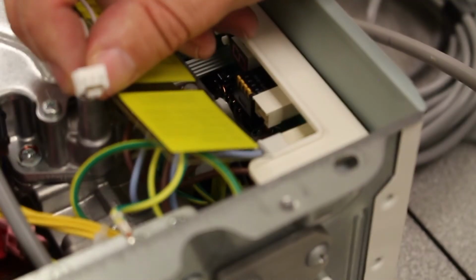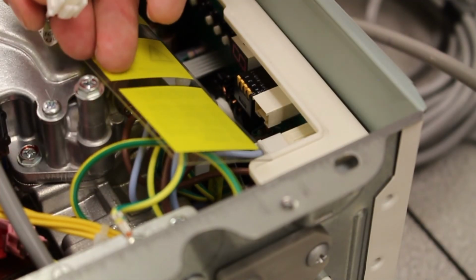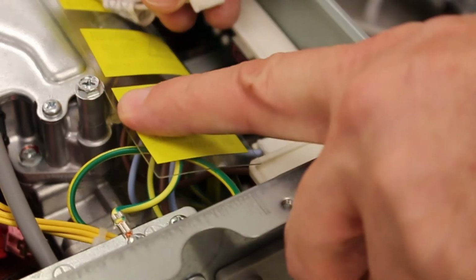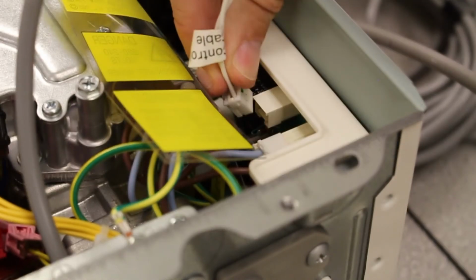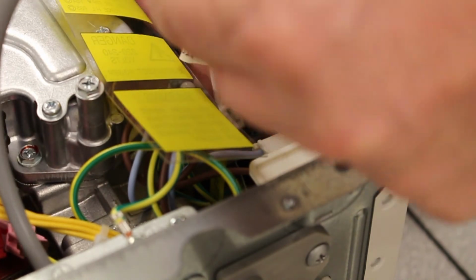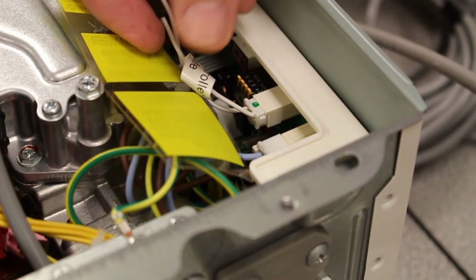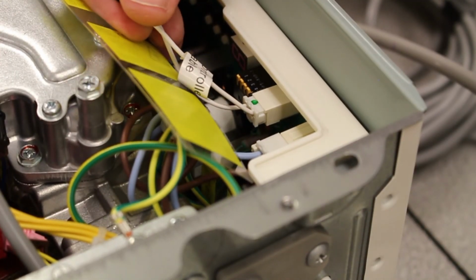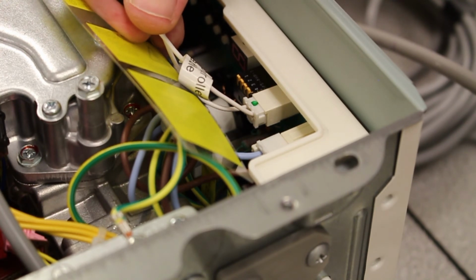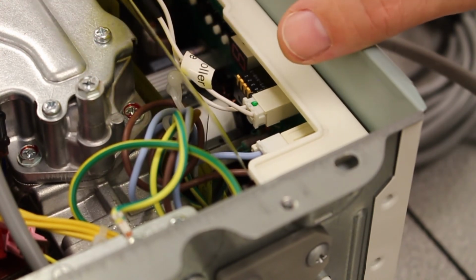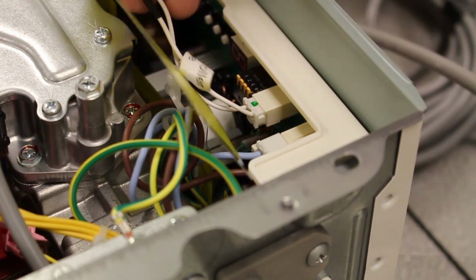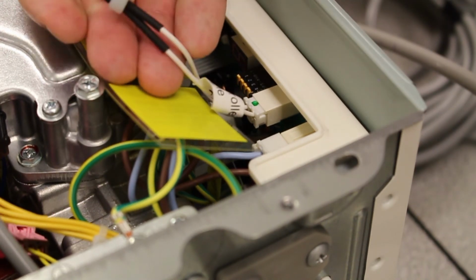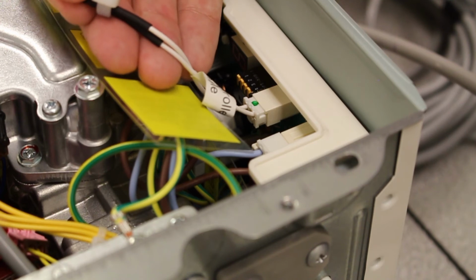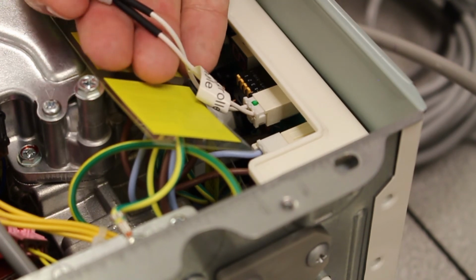So we've got the plug where we fed it through from underneath the unit, and then what we can do, let's get that out of the way, and we're just going to plug that in, down in here, like so, and that's the controller cable now plugged in and the controls will work. Now a couple of things, the unit will take up to 4 controllers. How do you terminate those? Simple, you just attach them, 4 controllers to the one controller cable. That works perfectly well. Here we've gone for a single cable.